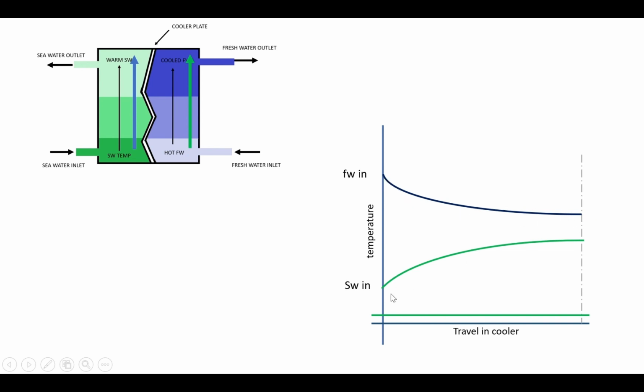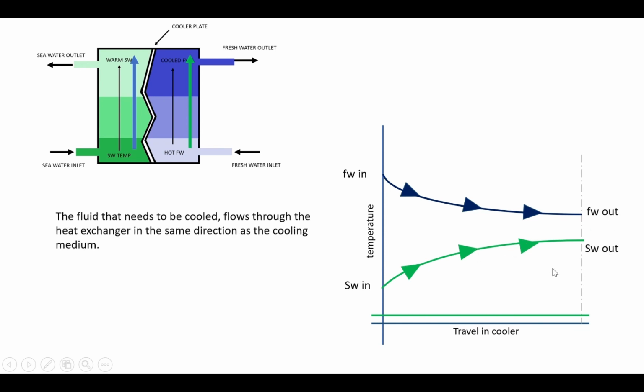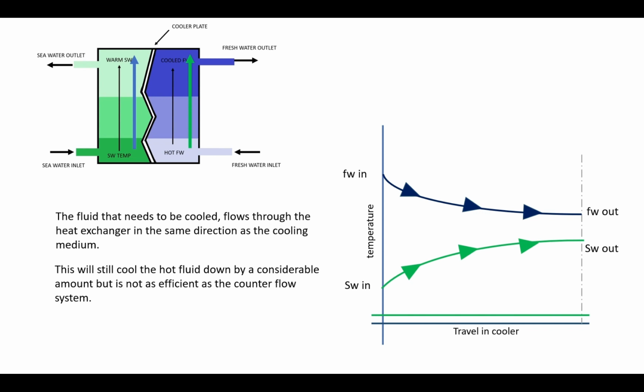Seawater temperature will slowly start to increase while it absorbs heat from the hot fresh water. The fresh water temperature will start to decrease as it passes through the cooler, but it will not decrease lower than the warm seawater temperature. The fluid that needs to be cooled down flows through the heat exchanger in the same direction as the cooling medium. This will cool the hot fluid down by a considerable amount but is not as efficient as the counterflow cooling system.